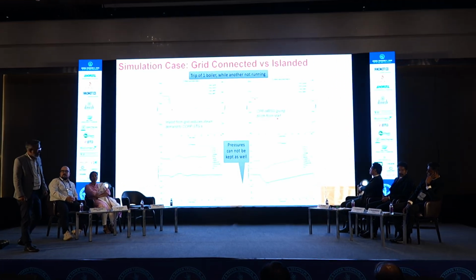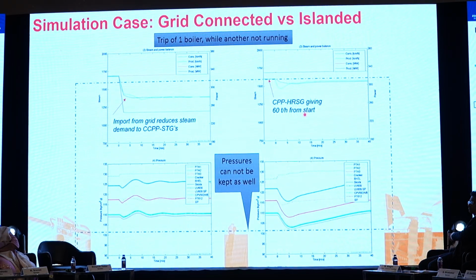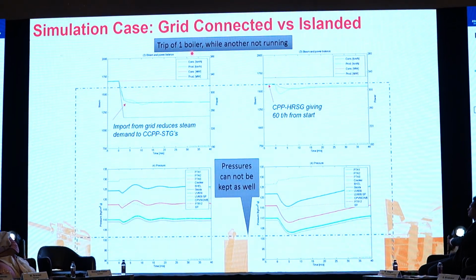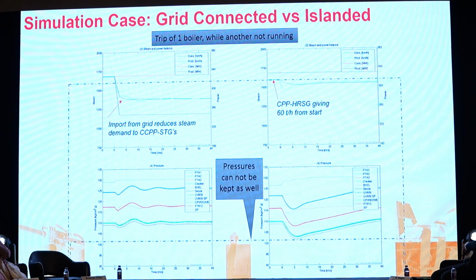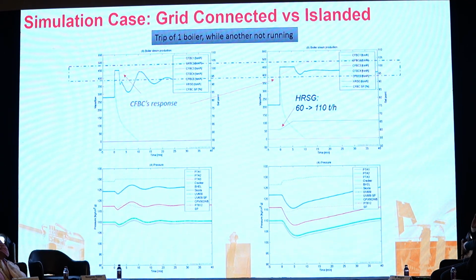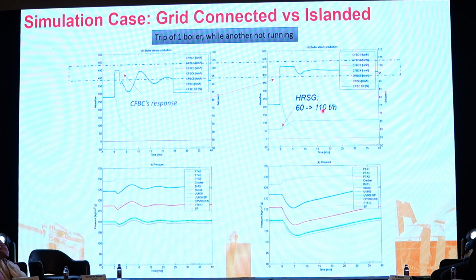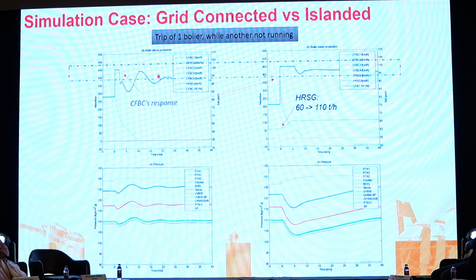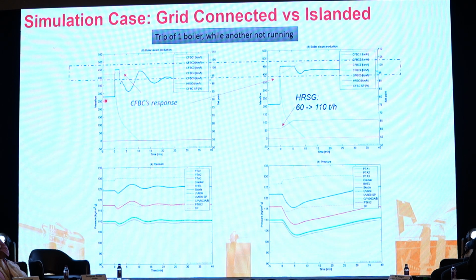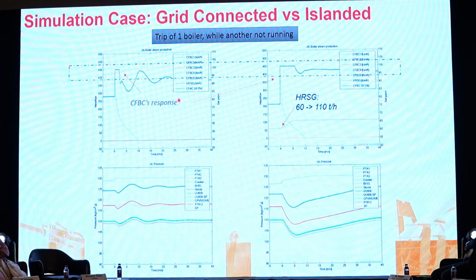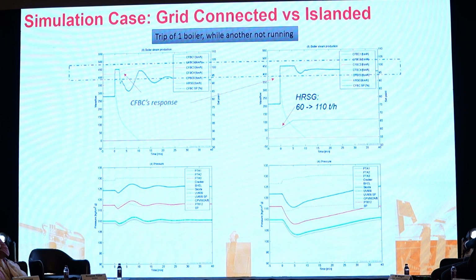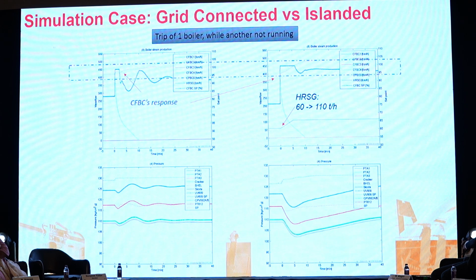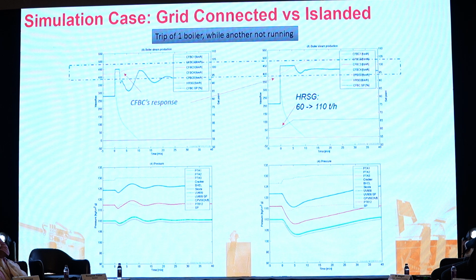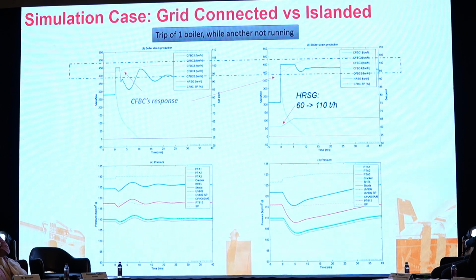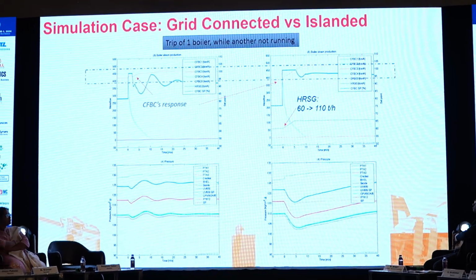But when the system is islanded, when we don't have the maneuverability to import power, there we have suggested that you already have one HRSG in place. So keep that HRSG in hot standby condition at 60 TPH from the start. And as soon as the other boiler gets tripped, ramp it up to 110 TPH, so that you compensate for the deficiency in the steam that arises in this particular scenario. And we also see the responses of the CFBC boilers, especially because this is their worst case scenario, because the boilers are almost getting saturated in this case when they ramp up to their maximum limit.